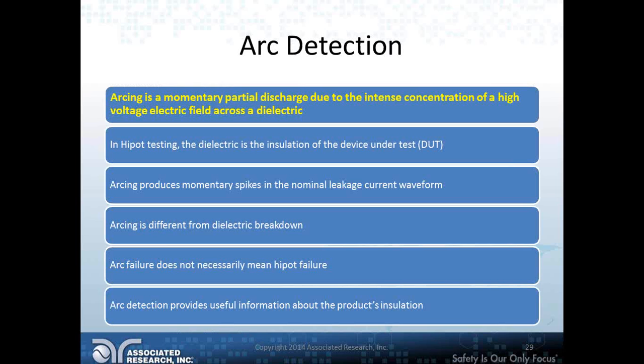Starting with arc detection: arcing is defined as a momentary partial discharge due to intense concentration of high voltage electric field across a dielectric. In Associated Research high pot testers, arc detection is a feature included within the high pot test itself — it is not a separate standalone test, but rather a test within a test.